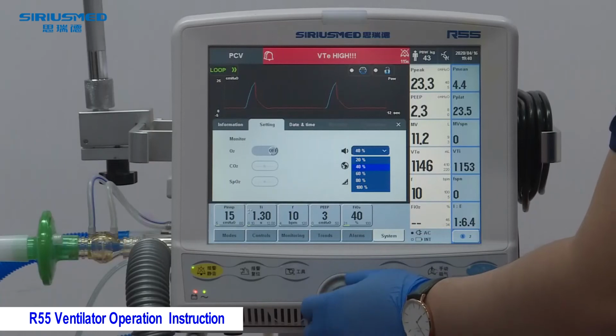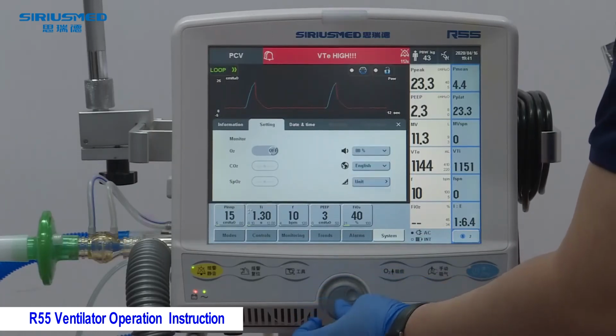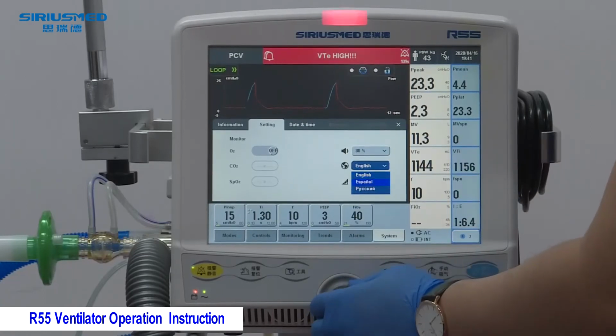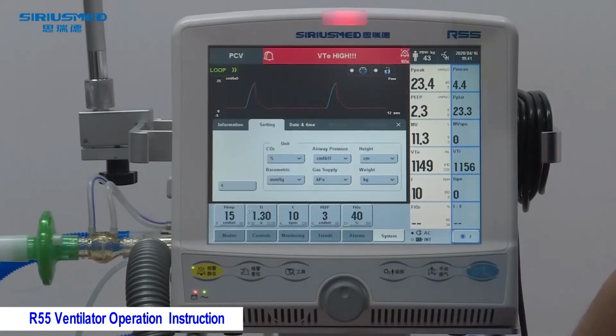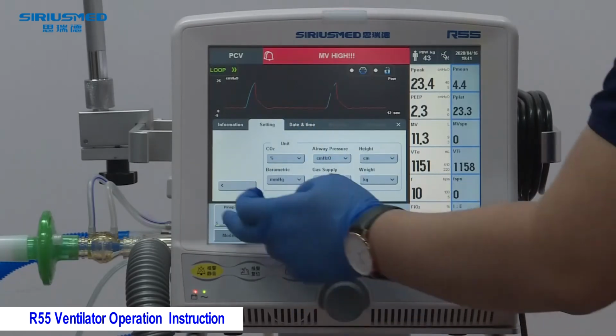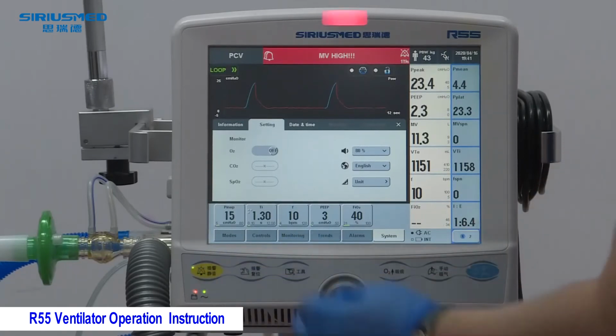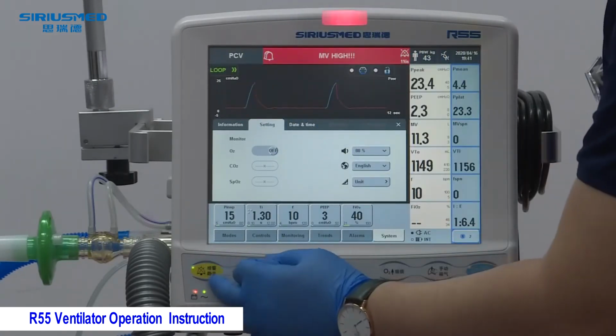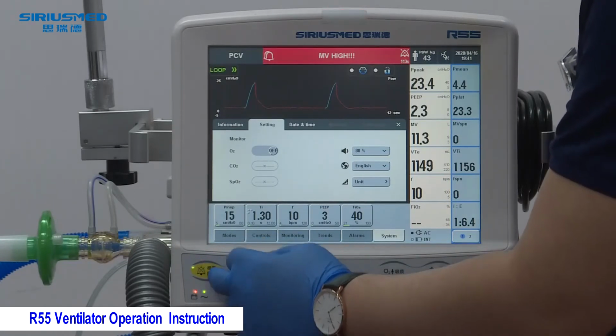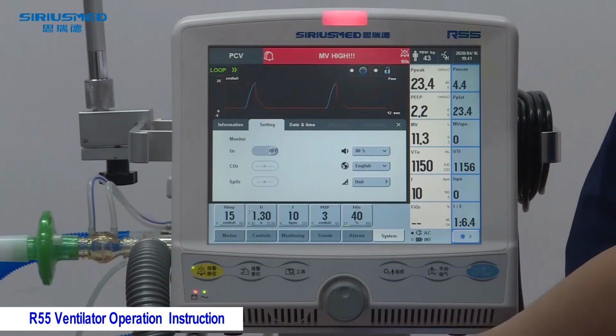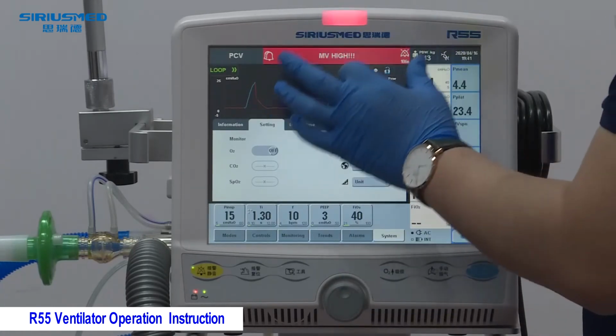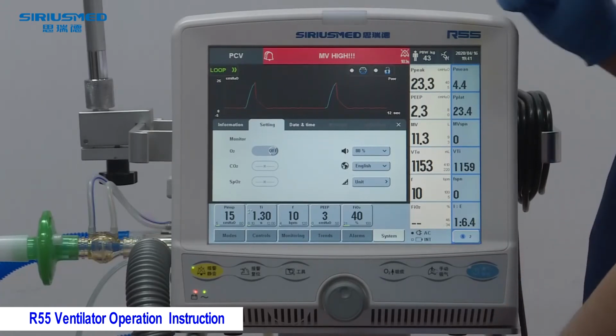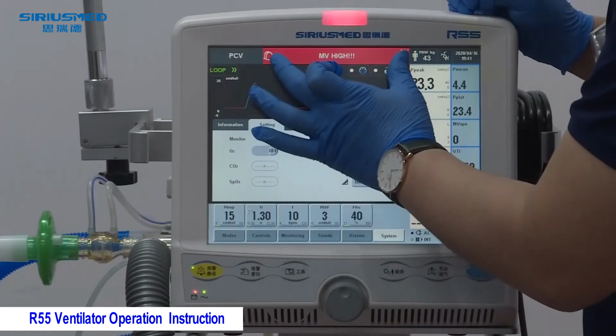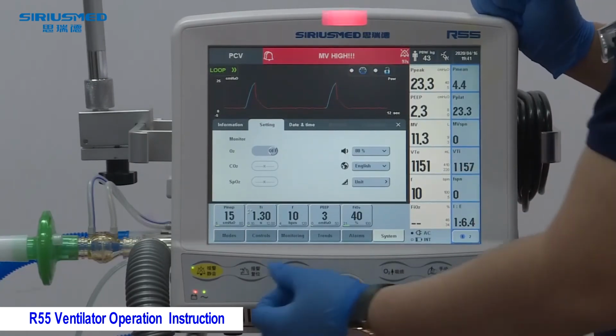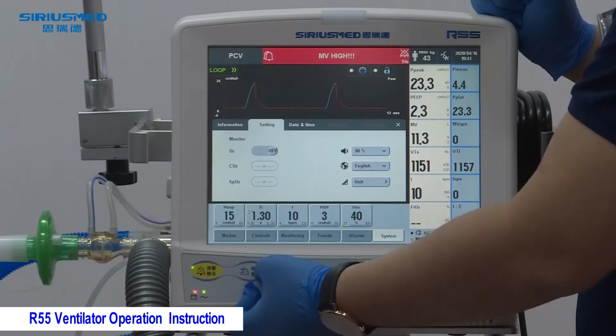And in this one is the log of the alarm. In this one you can change the language. And this one is the unit of, like, CO2 and pressure. And if there's an alarm, we can use the alarm silence button to silence the alarm for 2 minutes. And after the alarm disappears, the machine will also tell you what the alarm was, and show it on the screen. Then at that time, we can reset the alarm with the alarm reset.